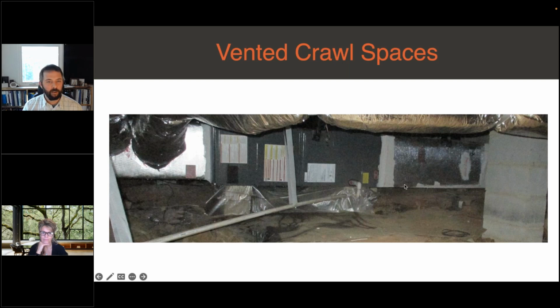This was an incentivized heat pump change out in a vented crawl space. What happened was they took out the original heat pump and put in new ductwork and this new heat pump. And they took the crawl space from being a vented, slightly conditioned crawl space to a vented wet crawl space. It was slightly conditioned before because of the amount of duct leakage that was in there.